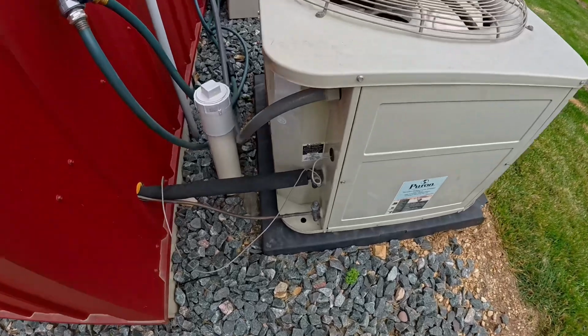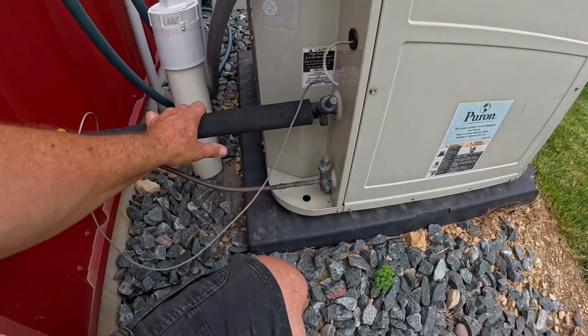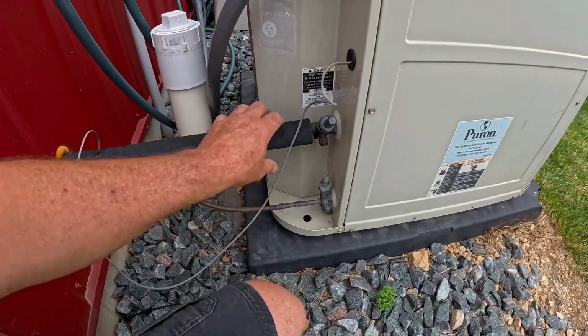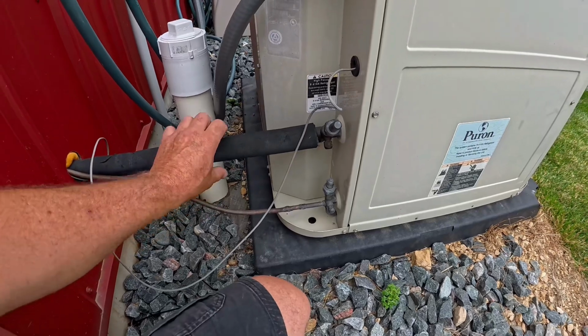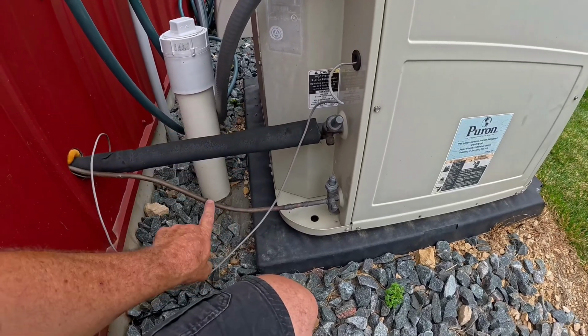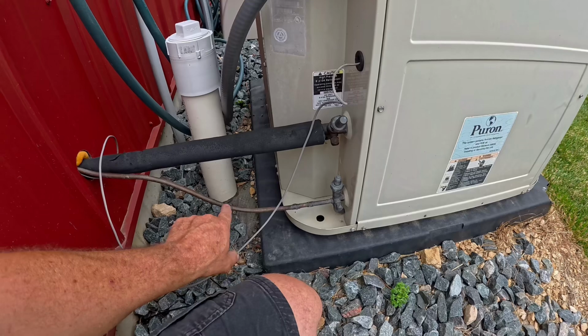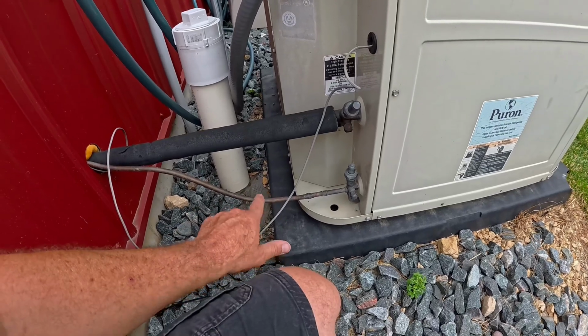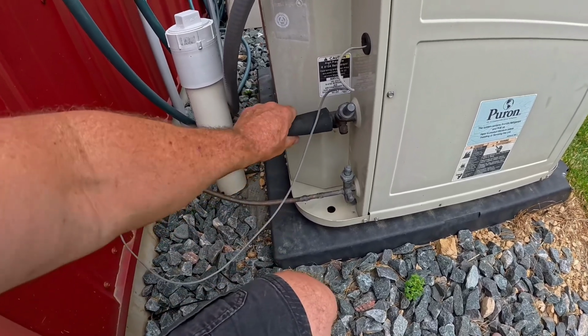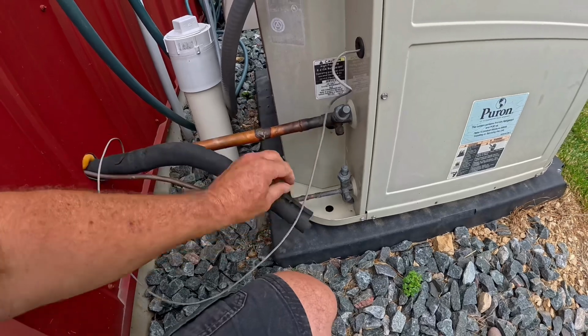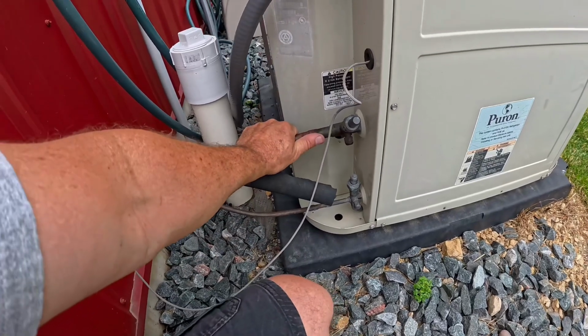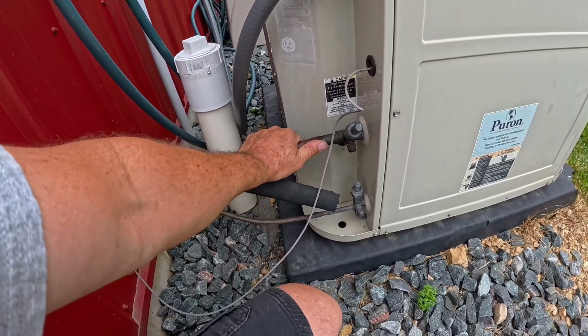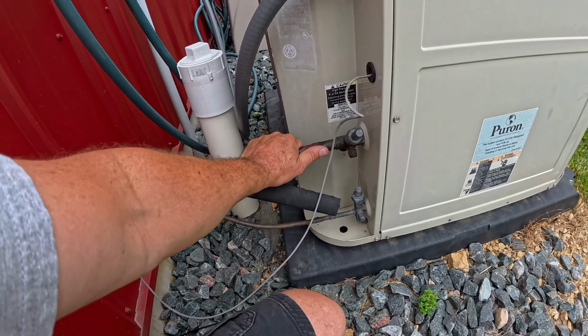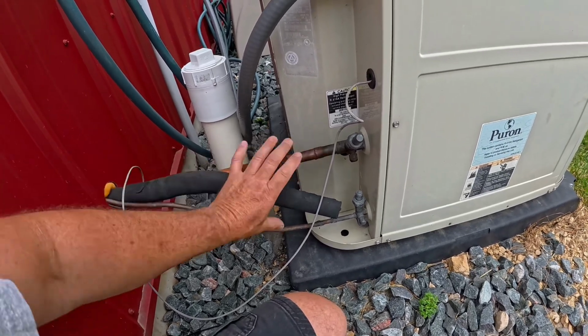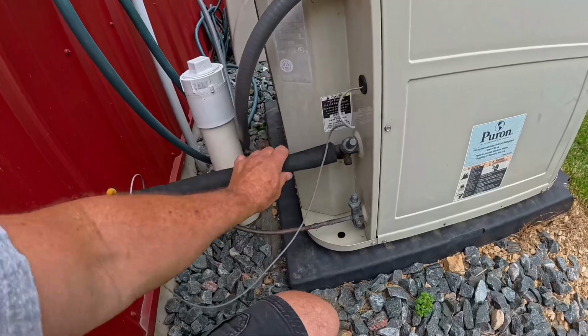The third easiest test and the quickest is basically to come out here to your line set. Obviously we got two lines. We got a large suction line covering insulation, and you got a smaller line, usually about a 3/8, and this one's hot. Try not to touch that one, it will burn you. This one up here is insulated for a reason. If you slide that insulation back and grab a hold of that line, if that line's as cold as you like your beer, it's usually a good sign it's running good. Put the insulation back on when you're done though.